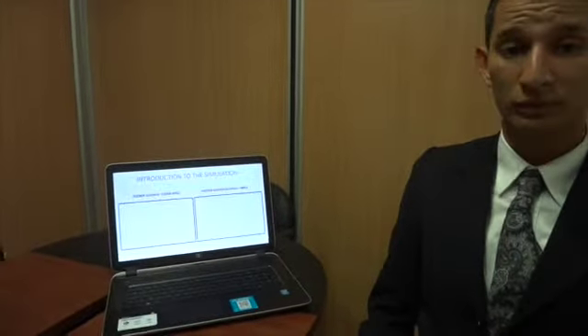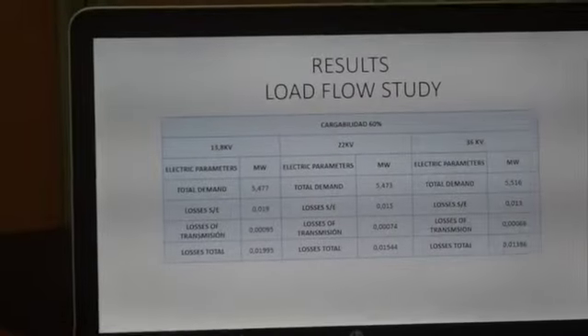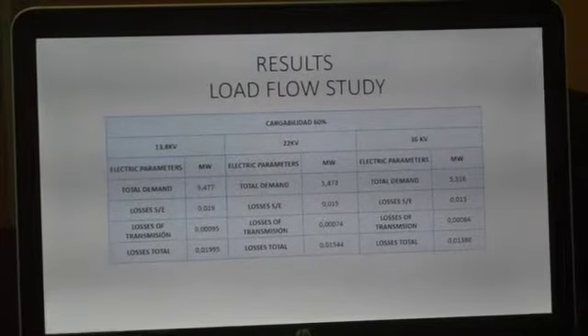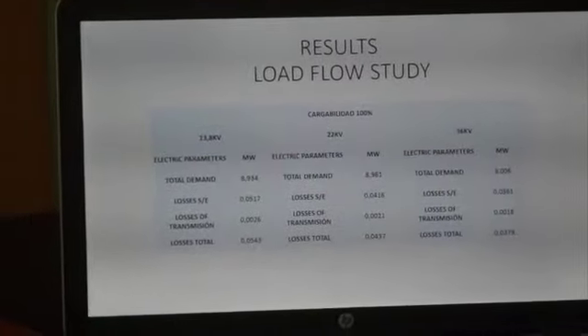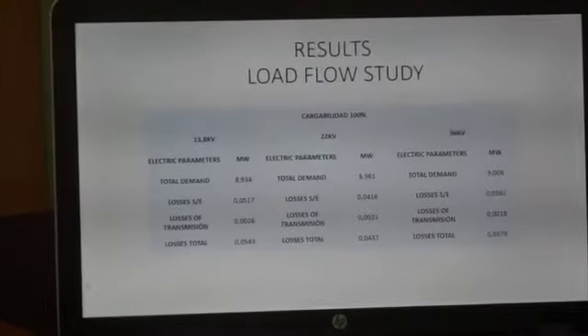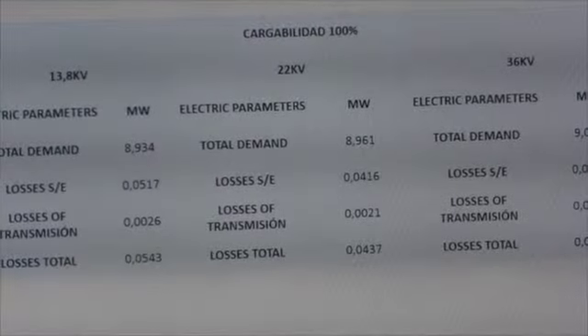For the simulation, the various load of the substation was taken, which is 4.8 megavolt amperes, and that is 60% of the rated capacity. You can see the result of the load flow study for the different voltage levels. Load 100%, 13.8 kV, 22 kV and 36 kV.